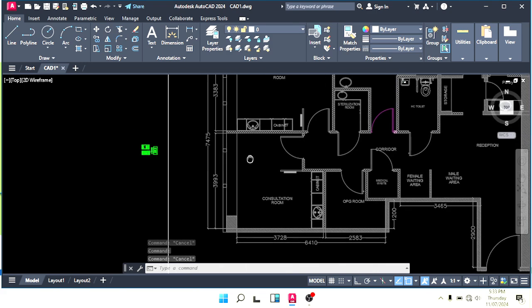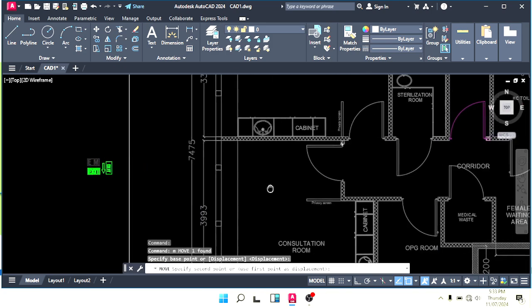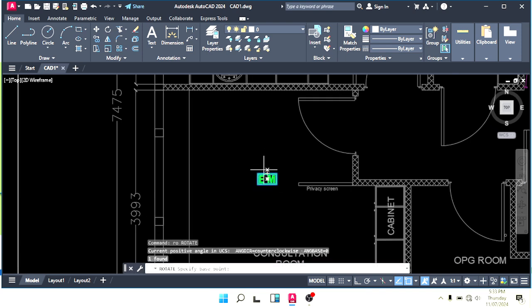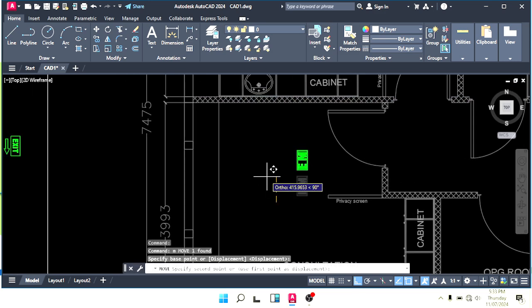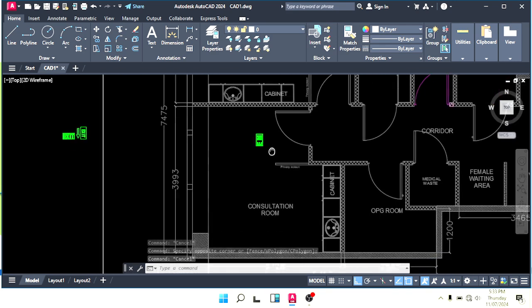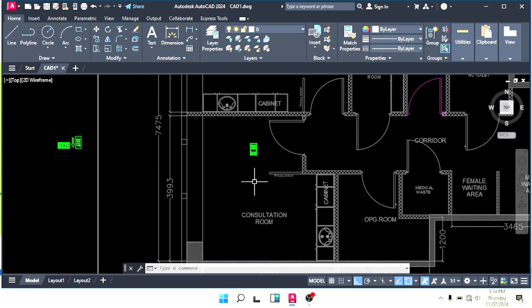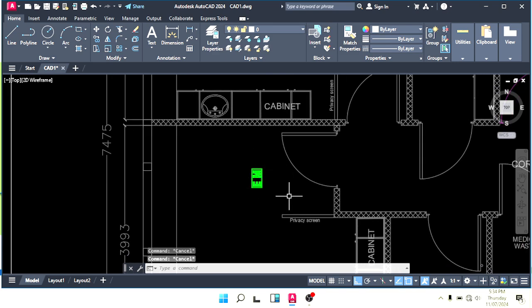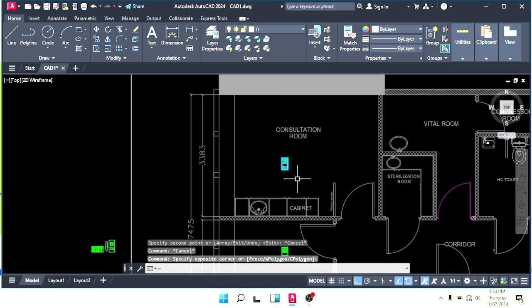Let's place it. For example, this is the consultation room — we have to make an emergency light here. Always try to keep the emergency light near the door, not in the center of the room. That is totally wrong. Some people put the emergency light in the center, but the right way is to keep it near the door.